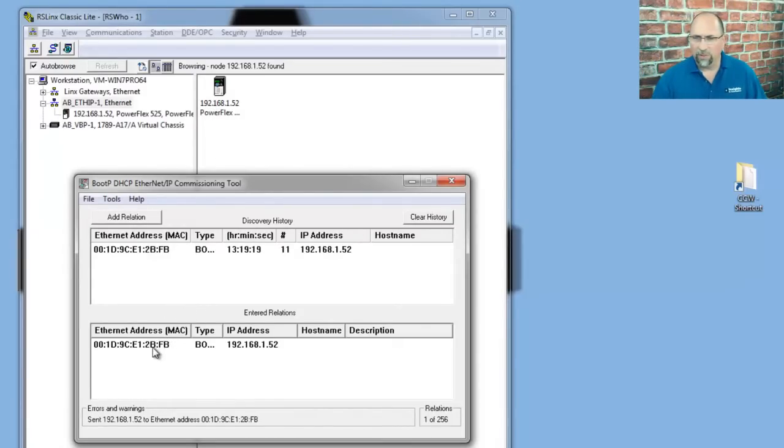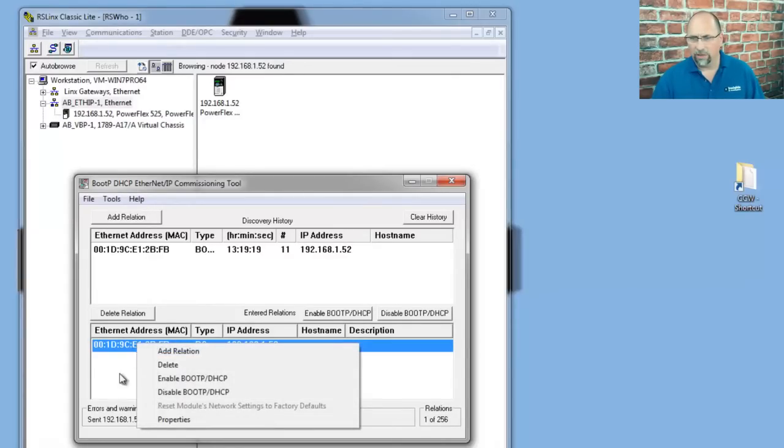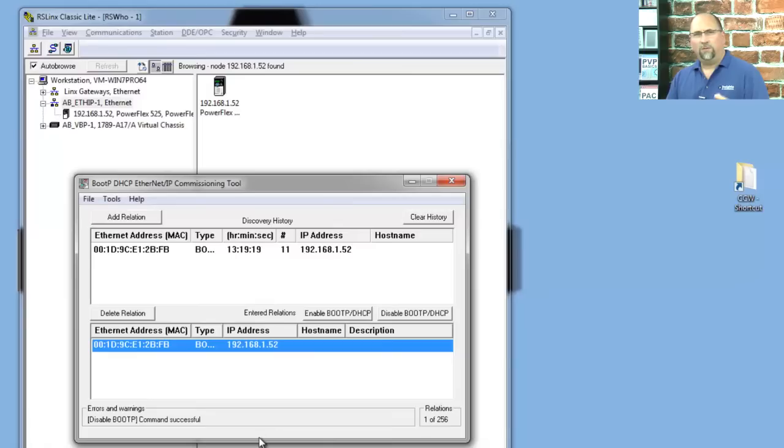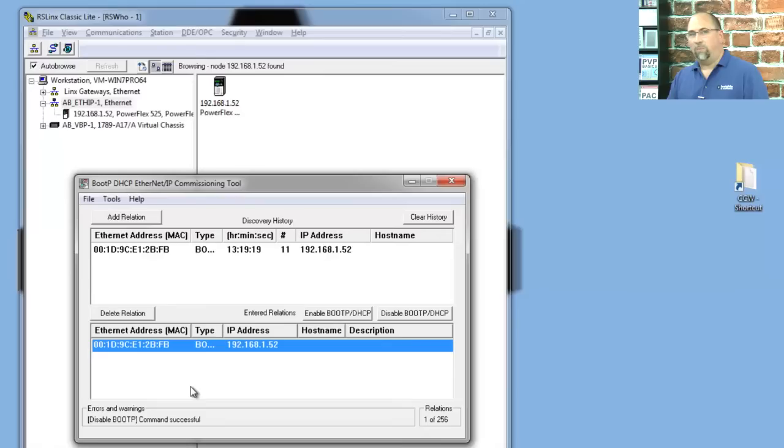Now, first, if I was going to do it from this utility, I would click here on the device in the RelationList and right-click and disable BOOTP. And you know if it's been successful when it comes up with this message that says command is successful. So we're done at that point. We can cycle power, and the drive will keep its IP address.